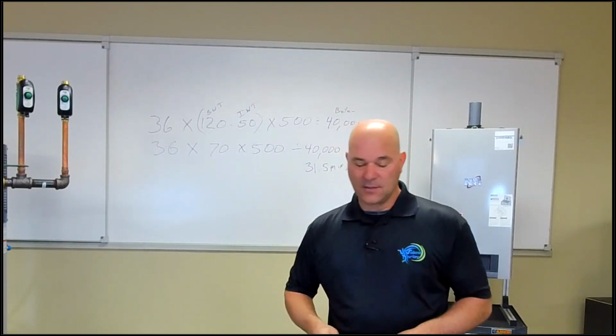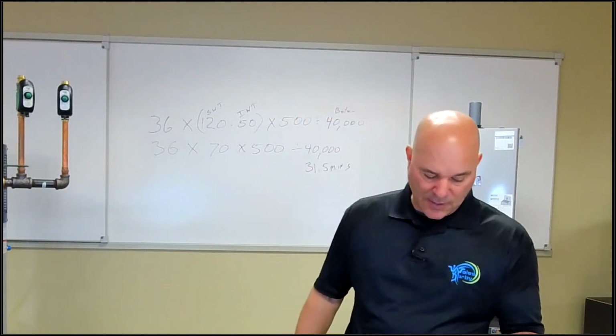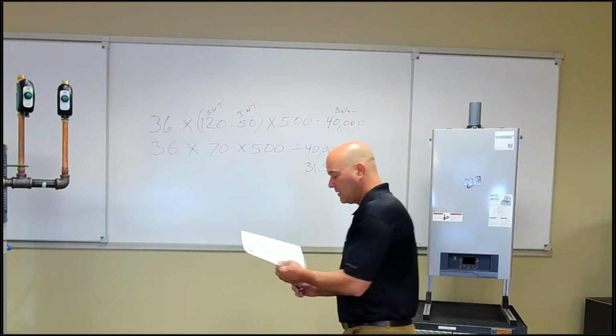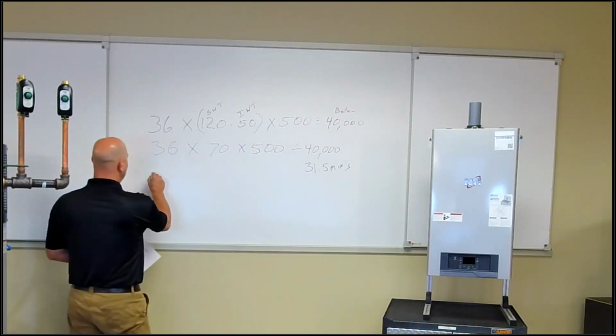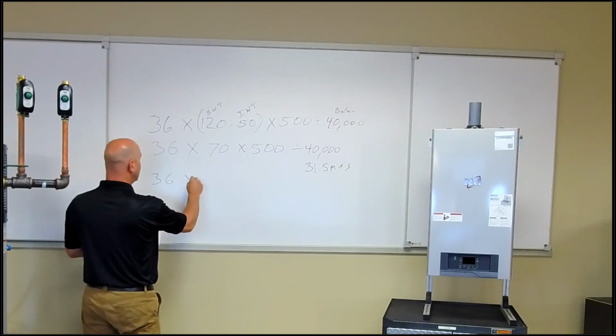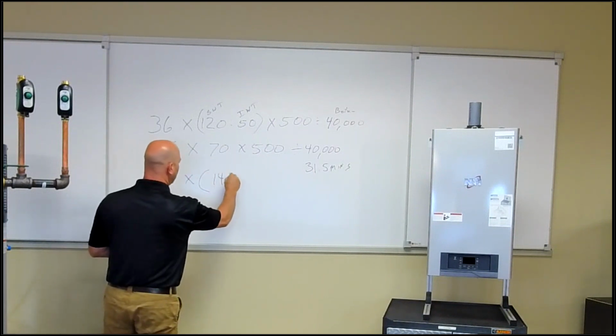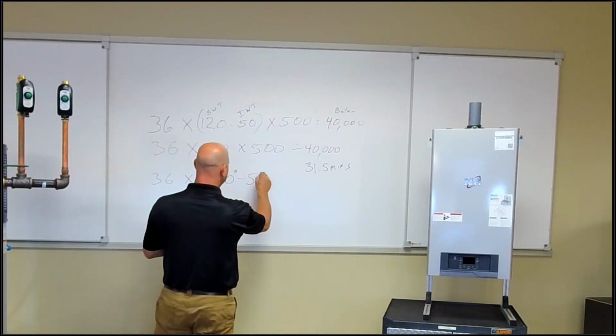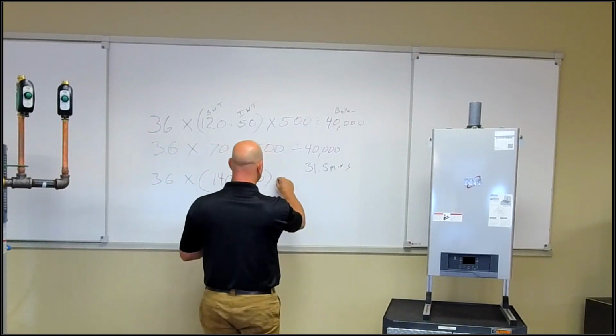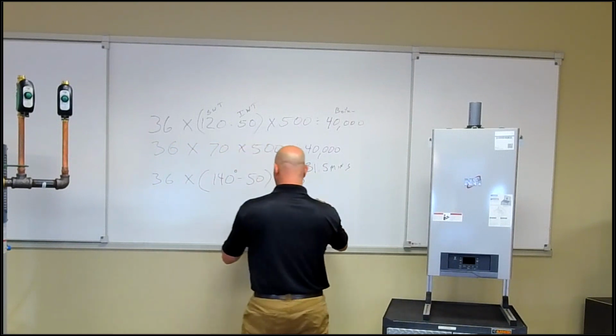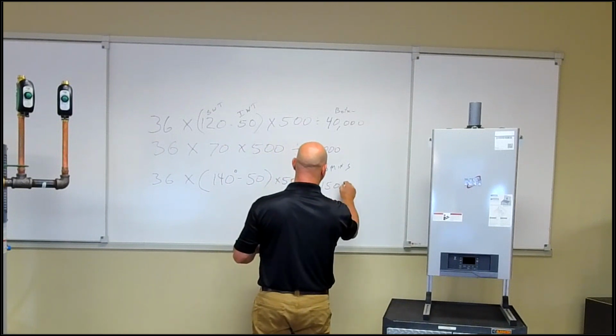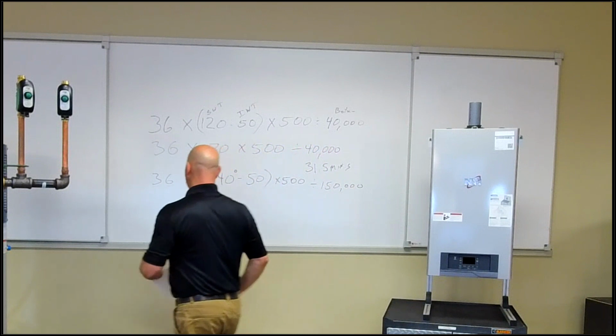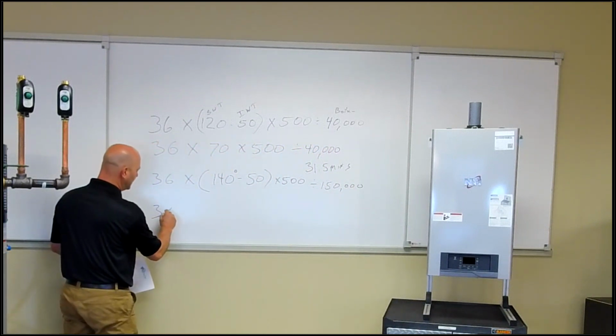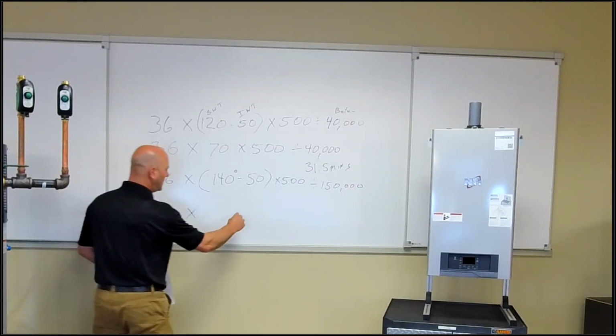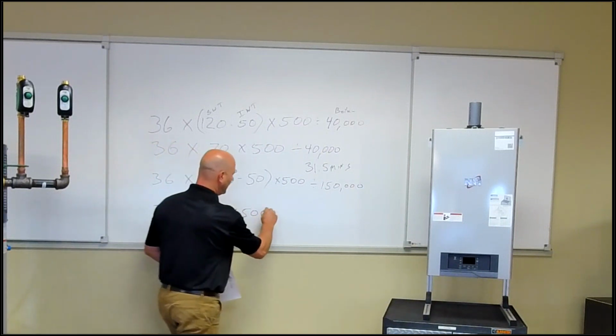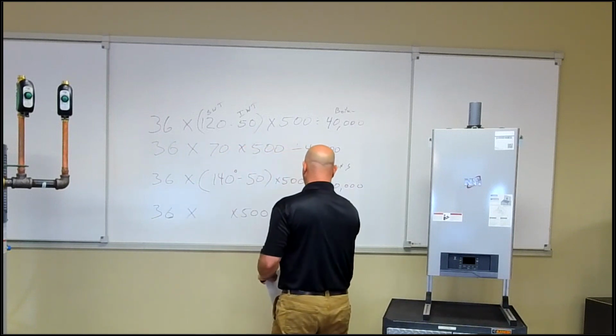Shoot Jim an answer. While you're shooting Jim some answers, I'm going to run you through another one. Okay? 36 times. Got 140 degree temperature we're looking for. 50 degree incoming water. Times 500. And we're going to drive this with a 150,000 BTU boiler. Okay? So somebody send Jim the answer to this one. 36 times what? Times 500 divided by 150,000 BTU.